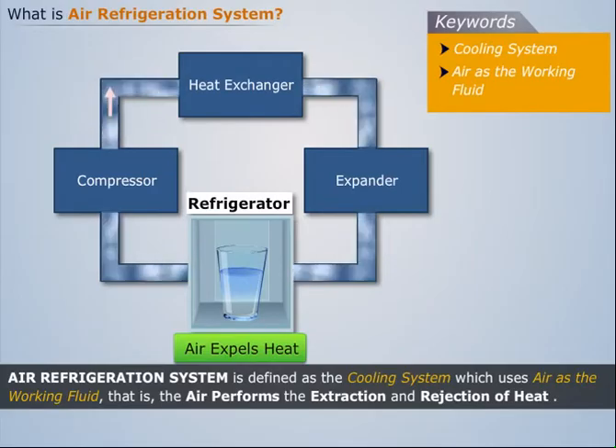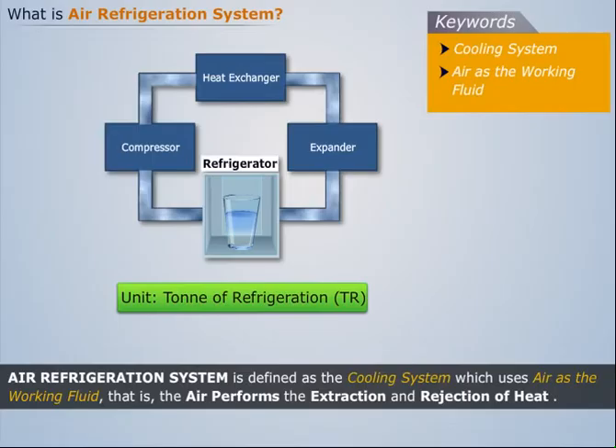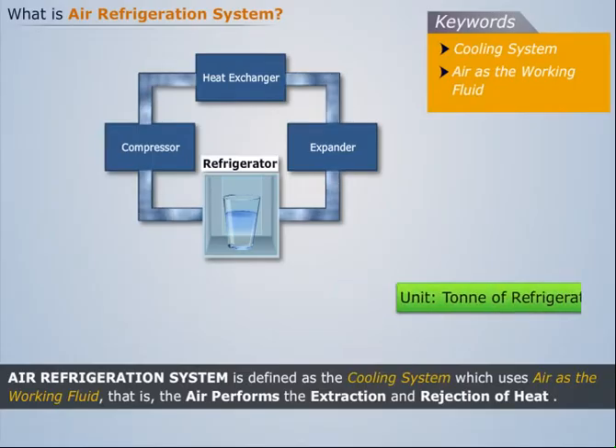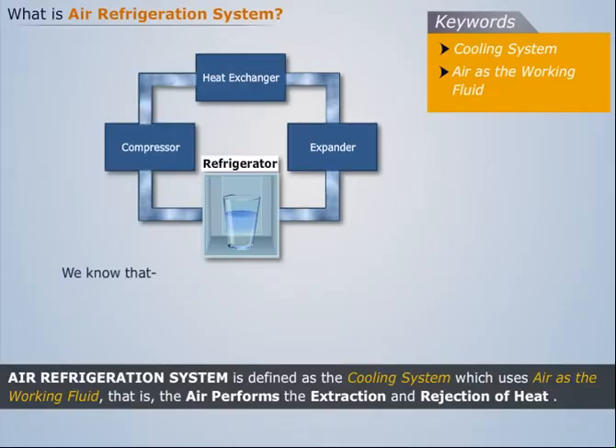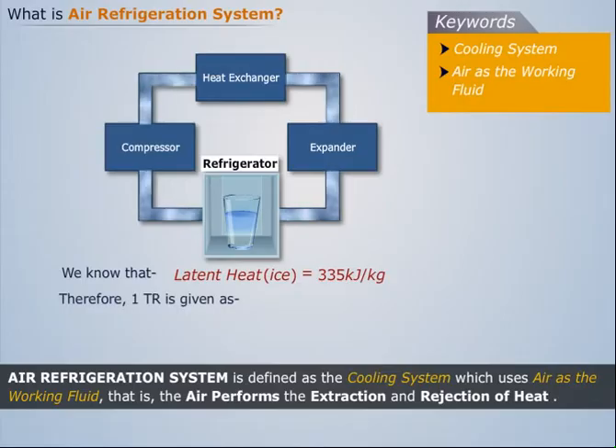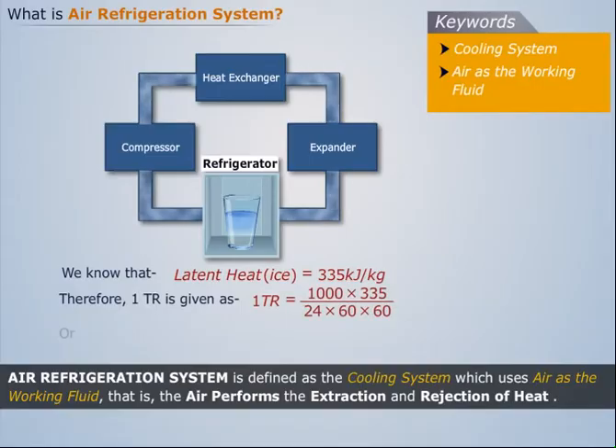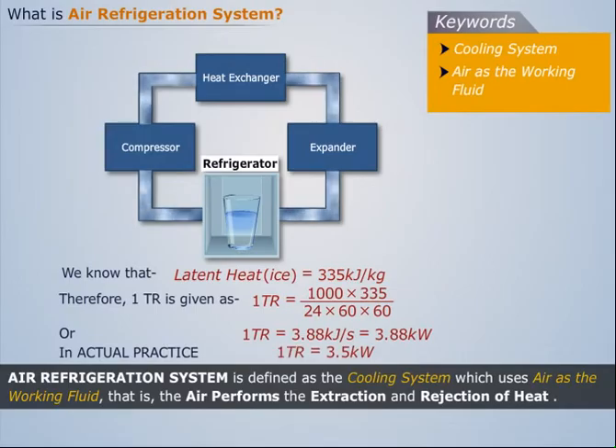The practical unit of this refrigeration is tonne of refrigeration (TR). A tonne of refrigeration is defined as the amount of refrigeration effect produced by uniform melting of one tonne of ice at zero degrees Celsius in 24 hours. As we know that latent heat of ice is equal to 335 kJ/kg, therefore one tonne of refrigeration can be calculated accordingly. However, in actual practice, one TR is equivalent to 3.5 kilowatt.